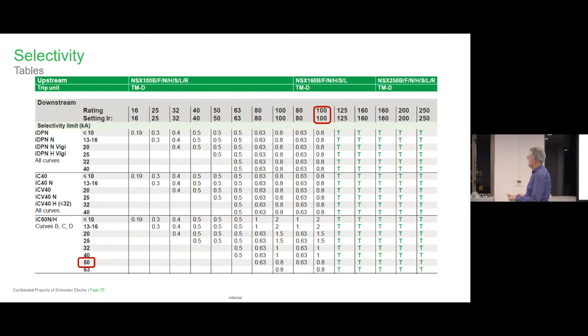NSX 160 can be a 100 amp trip with it. There's the IR setting. And downstream, we've just got an IC60, which is a miniature circuit breaker, 50 amp. And if we have a look at that, that is our partial discrimination level up to 0.8 kA. So it's not even 1 kA. That's a 6 kA device, but if we see a fault greater than that, it can trip out the upstream breaker. So that's not really ideal, is it?